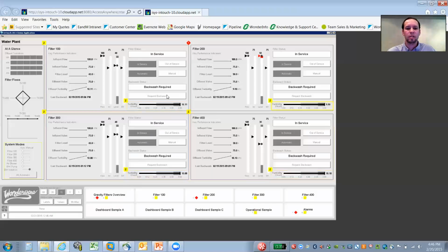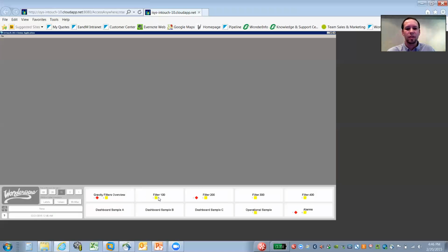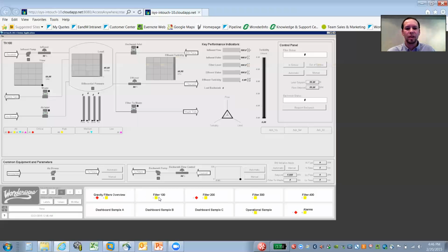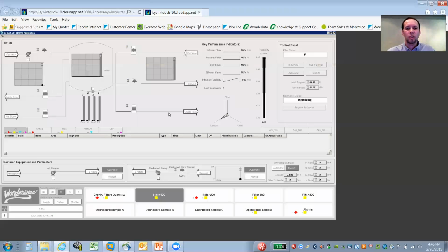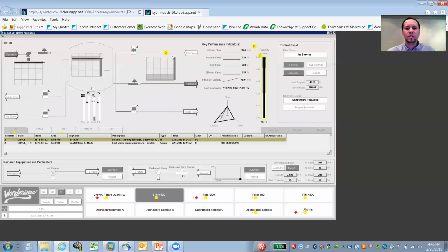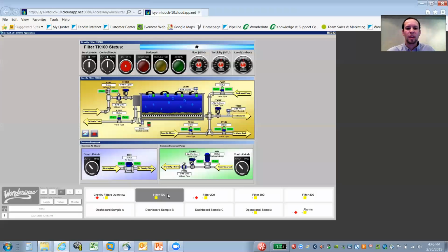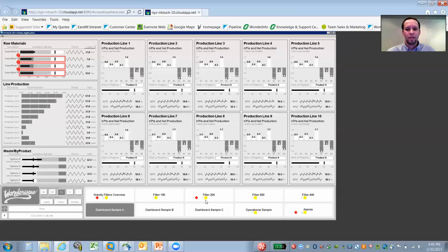This is a new library included with InTouch. We can see some examples here of how to build an effective operator display, really limiting the use of color only to when there's an alarm and we need to alert the operator's attention. So we see a yellow alarm border around some different areas of our plant that we need to focus our attention on. It really alerts the operator that we need to drill into this particular area of the plant so that we can make the appropriate decisions and actions. Here are a couple more example dashboards of what ArchestrA Graphics and Situational Awareness Graphics look like.